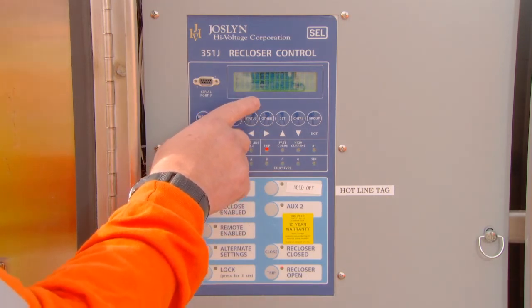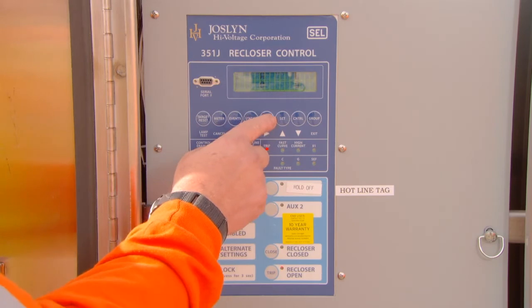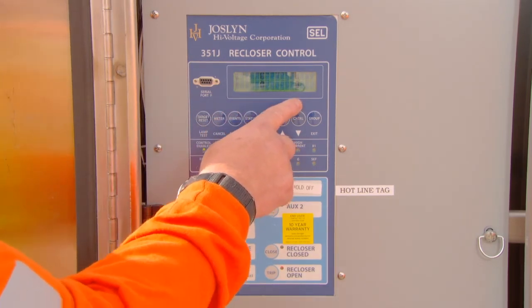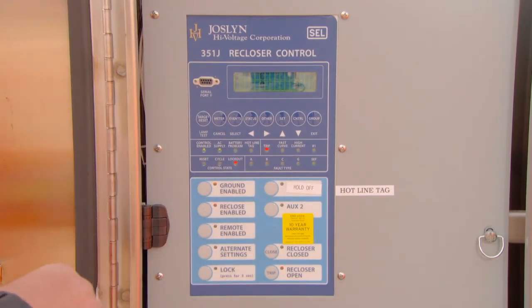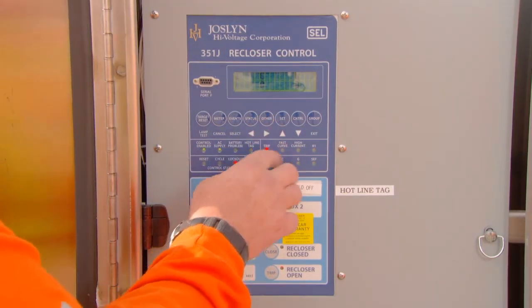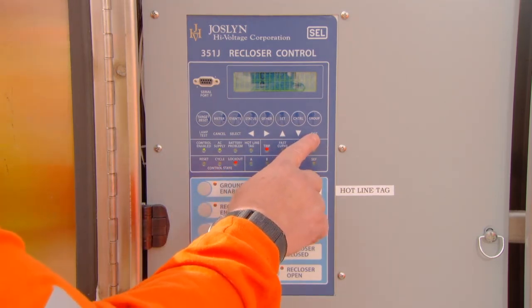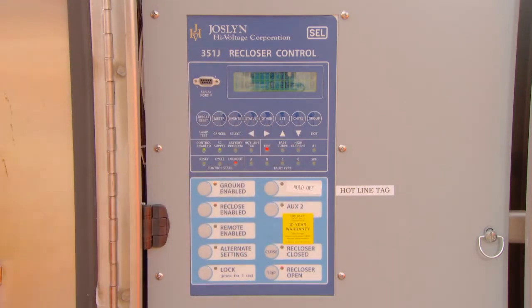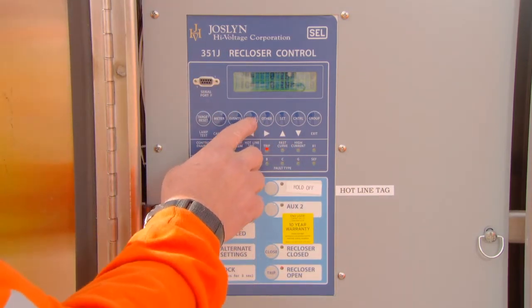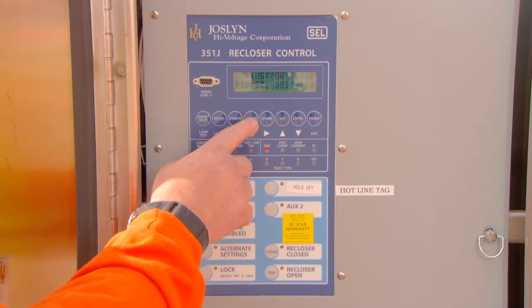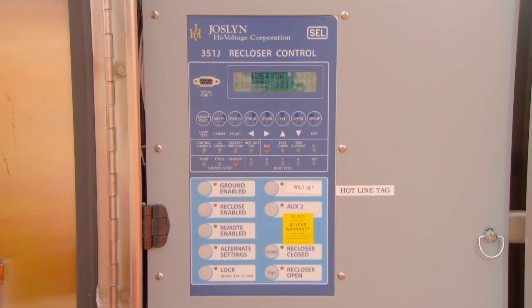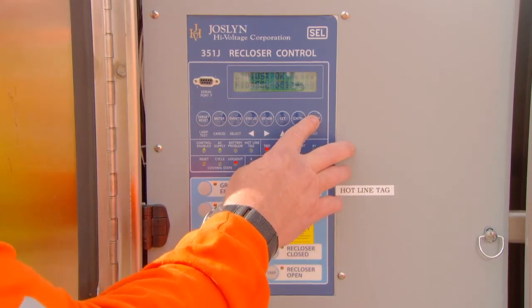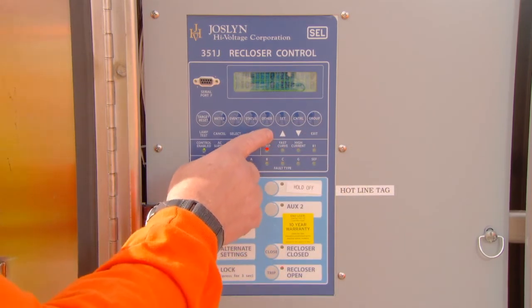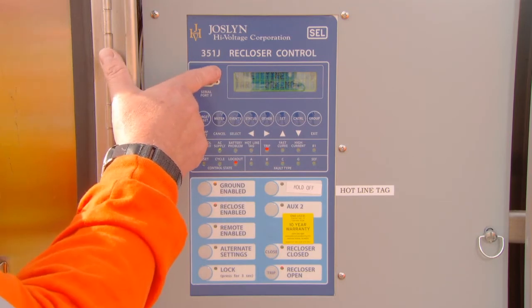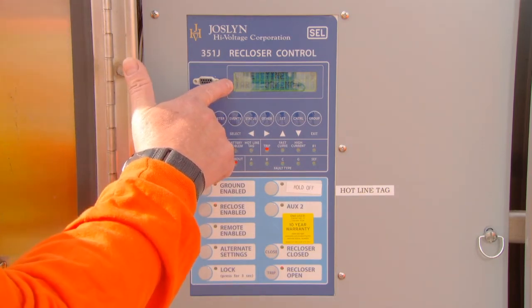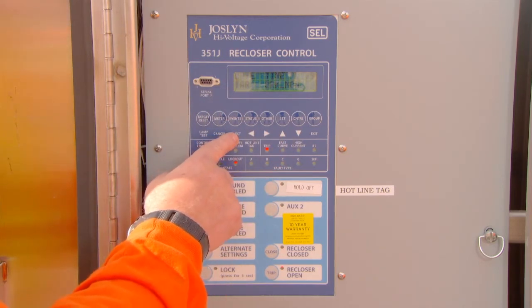Pressing the Other button or right arrow again will display the A and B phase amperages. Pressing Other again will display the C phase and the neutral amperages. These data are used to determine which phase caused the actual trip. To back out of any of these selections, press the Exit button, which is the redefined Group button, and you'll be returned to the main default screen. At the primary level, the Status button is just used to display the type of control and the serial number. At the secondary level, it functions as the left arrow button. Again, to back out of the Status selection, simply press the Group button that has been redefined to function as the Exit button.